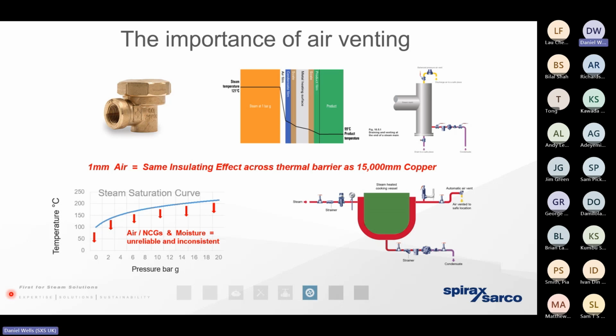So the best way for us to get the air out of the infrastructure is using a thermostatic air vent, never a mechanical air vent that we commonly use on a water-based system, because they work on the density principle. Air and water have got different densities. The problem is air and steam have got very, very similar densities. But because they've got different temperatures, that thermostatic principle works perfectly.